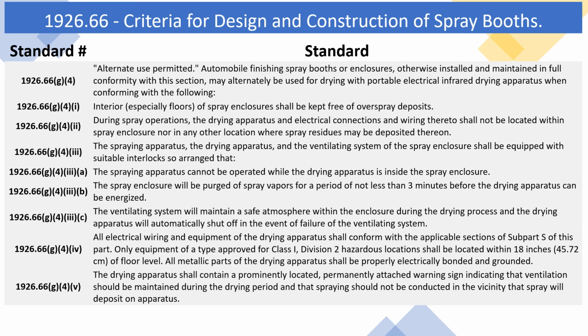1926.66 G4-4 All electrical wiring and equipment of the drying apparatus shall conform with the applicable sections of Subpart S of this part. Only equipment of a type approved for Class 1, Division 2 hazardous locations shall be located within 18 inches (45.72 centimeters) of floor level. All metallic parts of the drying apparatus shall be properly electrically bonded and grounded. G4-5 The drying apparatus shall contain a prominently located, permanently attached warning sign indicating that ventilation should be maintained during the drying period and that spraying should not be conducted in the vicinity where spray will deposit on the apparatus.